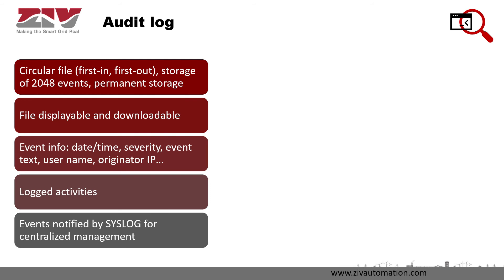Last but not least, it's crucial to have good cybersecurity event generation and management — what we call audit log. Cybersecurity events enable compliance with one of the basic concepts of cybersecurity: non-repudiation, which consists in avoiding denying that a device performed an action that it did, or claiming that a device performed an action that it didn't. The cybersecurity events are stored in a circular FIFO file with capacity for more than 2048 events, and it's permanently stored.